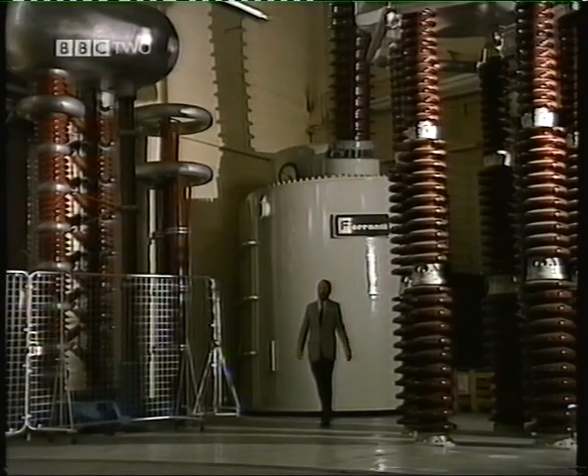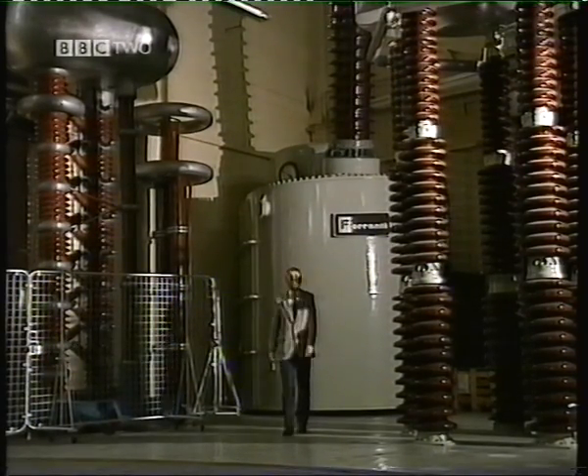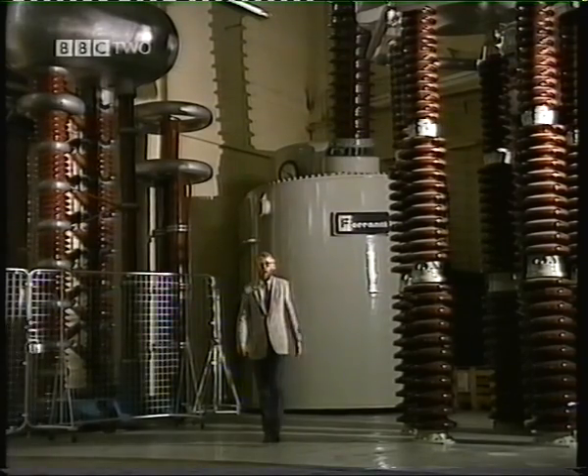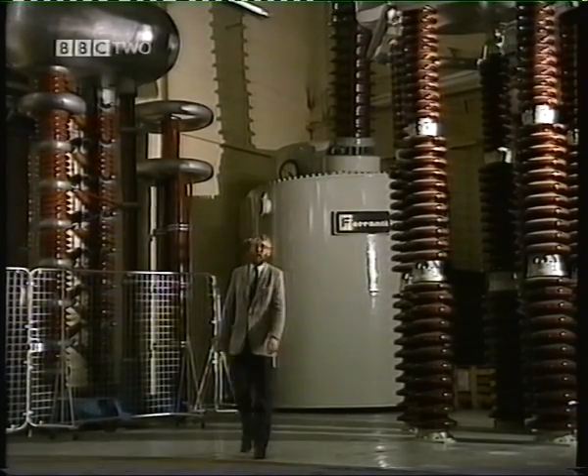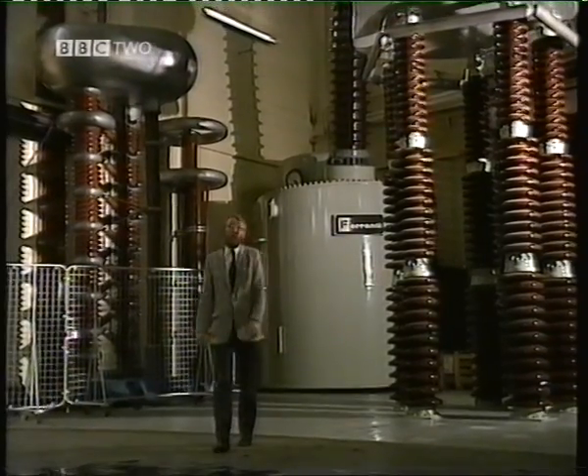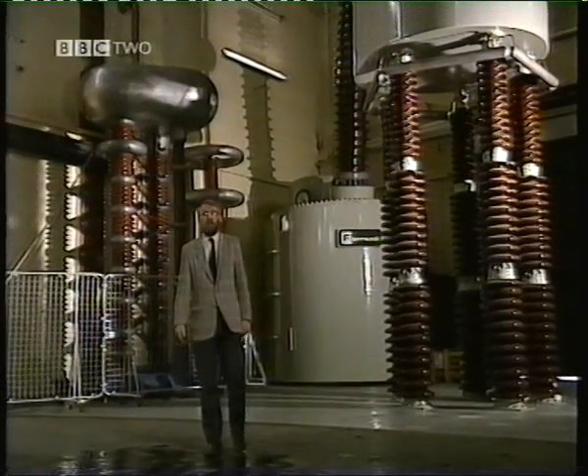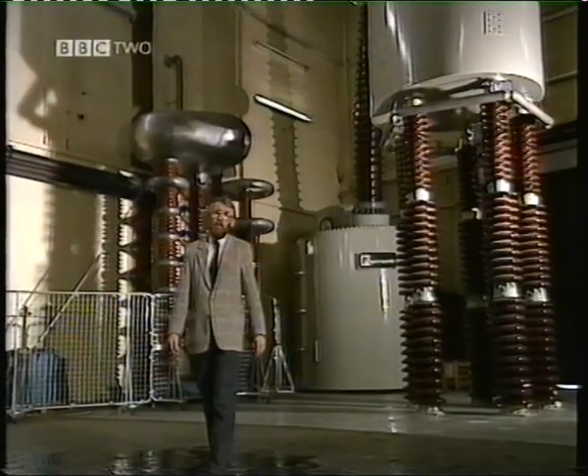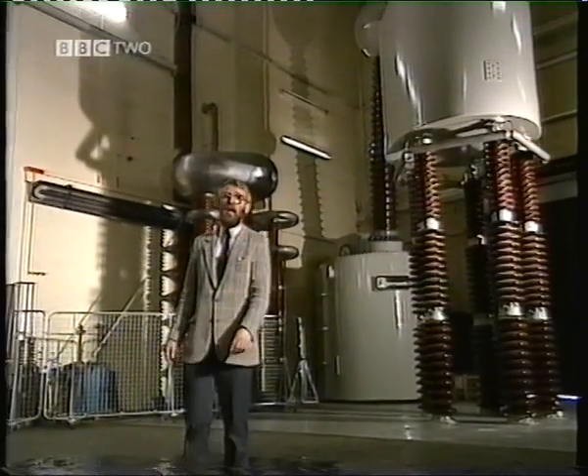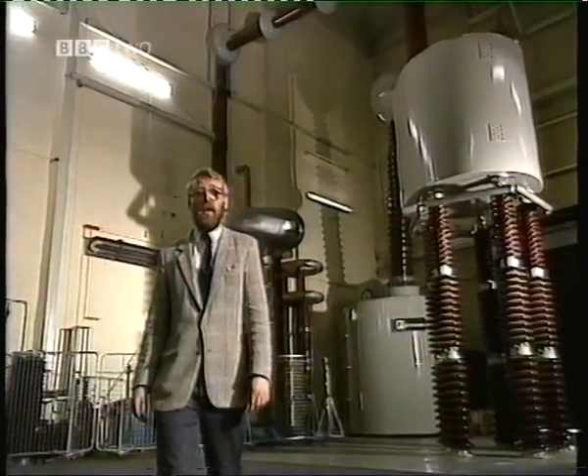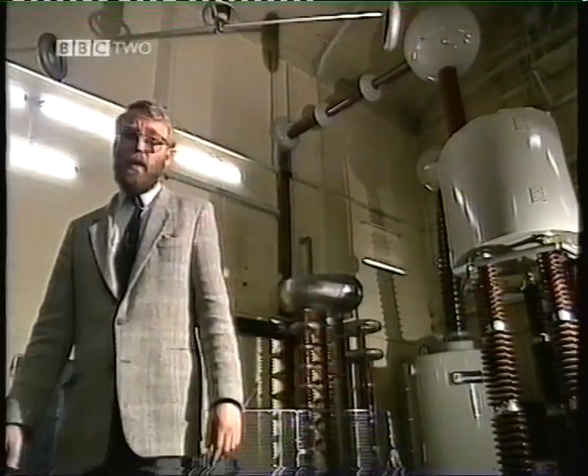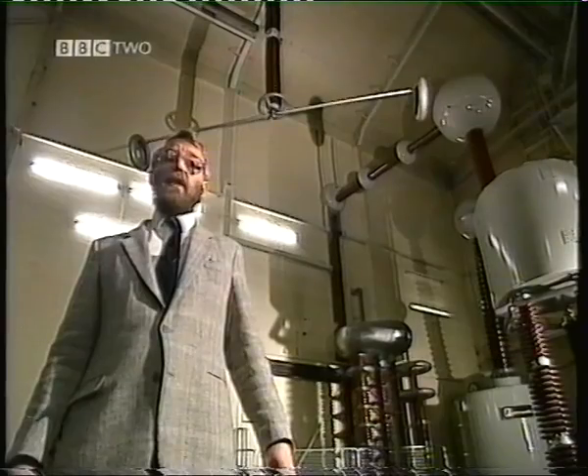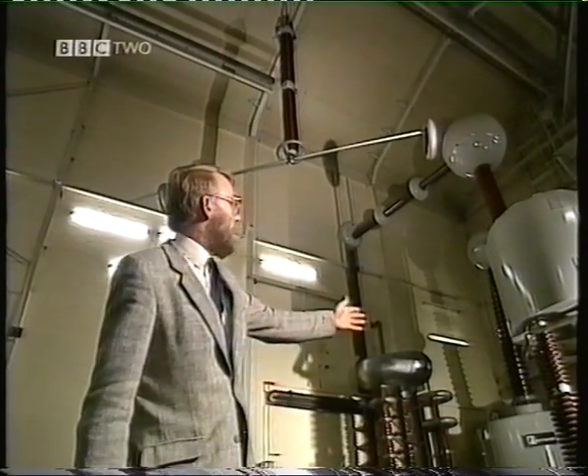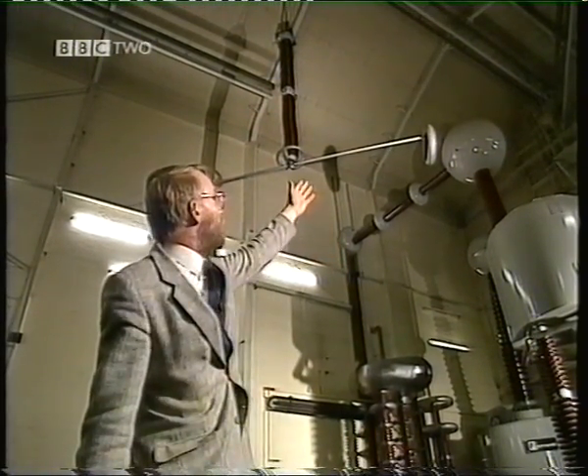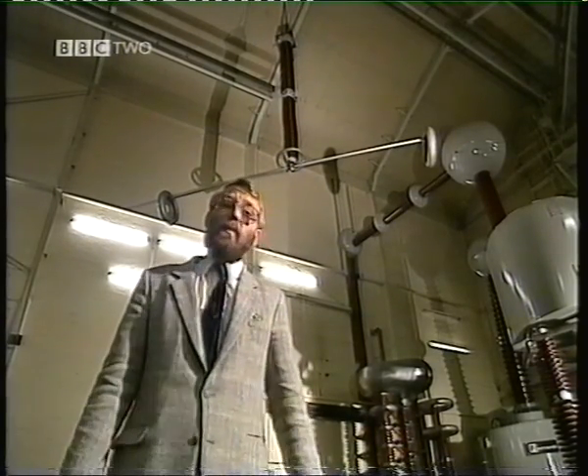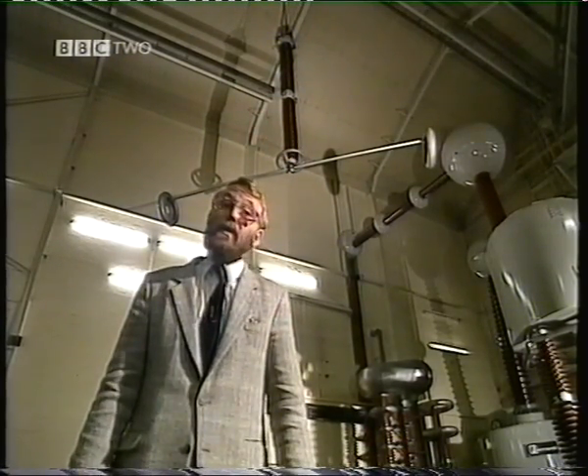One of the biggest electrical problems for power systems is associated with voltage surges when there are switchings or lightning strikes to the system. Much of the additional ironmongery at pylons and power stations is associated with this. This laboratory is set up to simulate some of those high fault voltages. The large grey transformer behind me produces about 800 kilovolts, and that's further stepped up by the transformer standing on the insulating legs there, so that on the big sphere at the top over 1,000,000 volts can be produced. That's more than twice the service voltage.